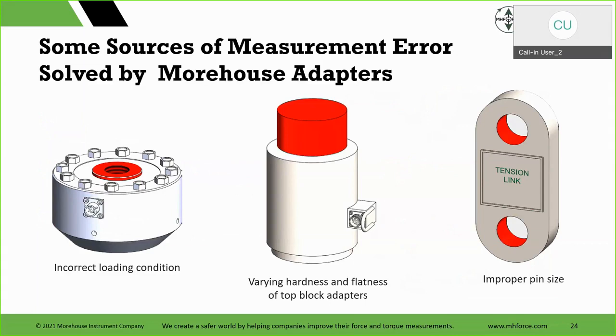So, some additional errors, incorrect loading condition here. Well, it's not really incorrect. The problem here is without this adapter, you're in the force lab, a customer has this cell, and if they don't send their adapter, the depth of the thread engagement determines the output of the load cell. So the conversation needs to be, hey, what are you using on top? Are you loading against the shoulder? Do you have a 1 inch? Are you putting 1 inch engagement on there? That discussion often raises a lot of eyebrows.